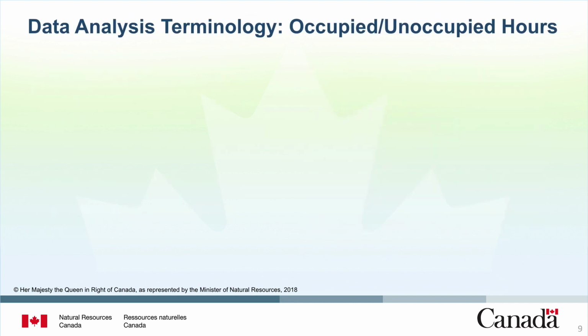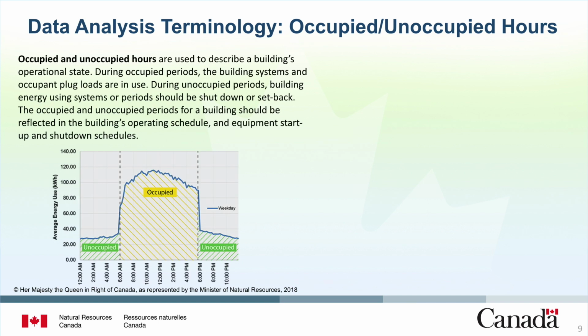The final key terms are occupied and unoccupied hours. Occupied/unoccupied hours are used to describe a building's operational state. During occupied periods, the building systems and occupant plug loads are in use. During unoccupied periods, building energy use systems should be shut down or set back. The occupied and unoccupied periods for a building should be reflected in the building's operating schedule and equipment startup and shutdown schedules.